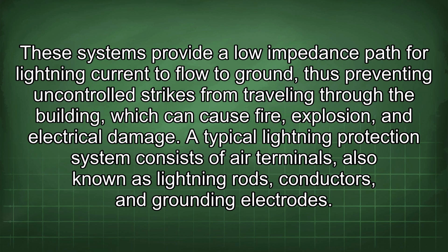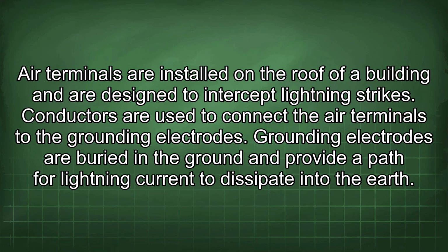A typical lightning protection system consists of air terminals, also known as lightning rods, conductors, and grounding electrodes. Air terminals are installed on the roof of a building and are designed to intercept lightning strikes. Conductors are used to connect the air terminals to the grounding electrodes. Grounding electrodes are buried in the ground and provide a path for lightning current to dissipate into the earth.